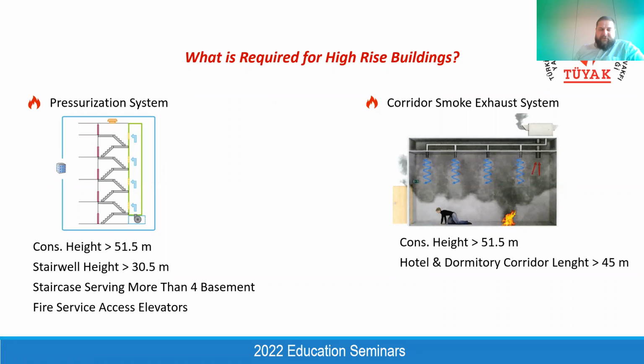From the mechanical point of view, but the smoke, it is the smoke issue. The pressurization systems become mandatory if the construction height exceeds 51.5 meters, or even if our building is not exceeding 51.5 meters, if the stairwell height exceeds 30.5 meters, or if the stairwell serves more than 4 basement floors, the pressurization system becomes mandatory as per Turkish fire code.